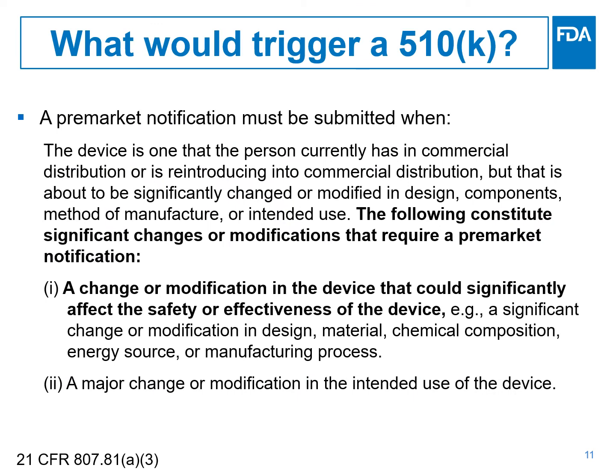So the question is, what type of changes will trigger a 510K? The FDA guidance does not provide a definite answer for all devices, but rather overarching concepts and principles that manufacturers should consider in their decision-making process. The regulatory criteria in 21 CFR 807.81 state that the premarket notification must be submitted specifically when a change or modification in the device could significantly affect the safety or effectiveness of the device. For example, a significant change or modification in design, material, chemical composition, energy source, or manufacturing process.